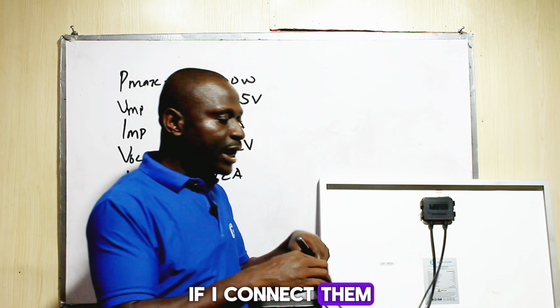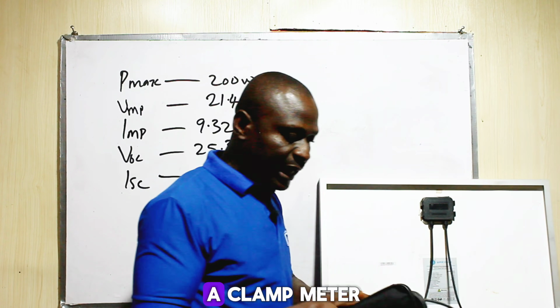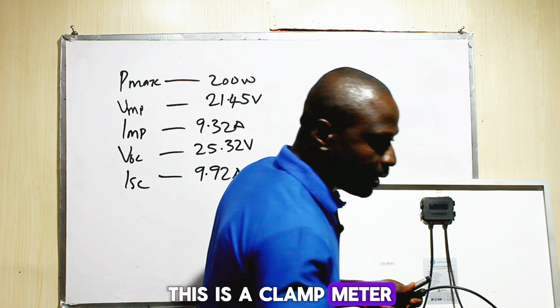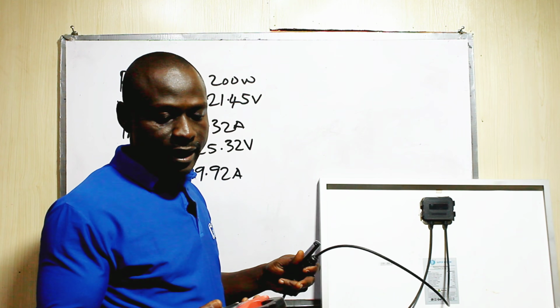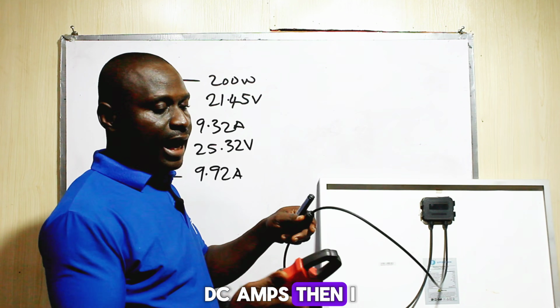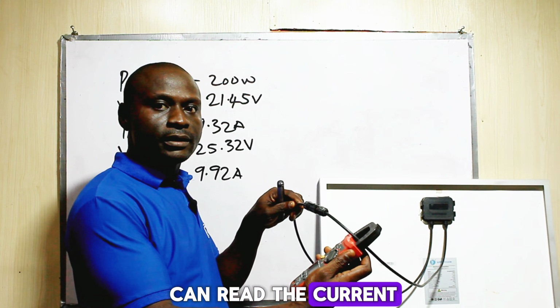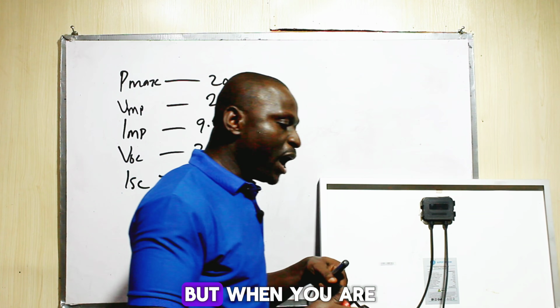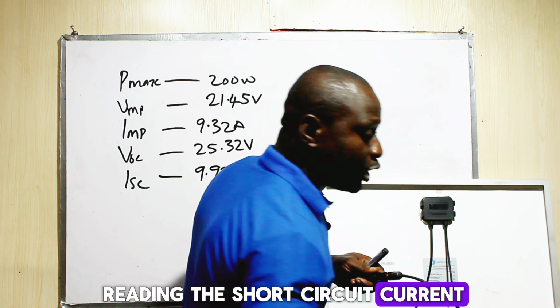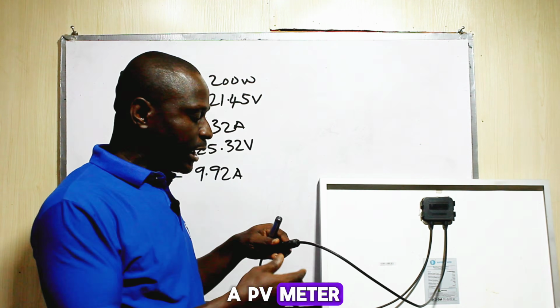If I connect them like this, I will now use a clamp meter, set it to DC amps, and I can read the short circuit current. But when reading the short circuit current, you can also use a PV meter.